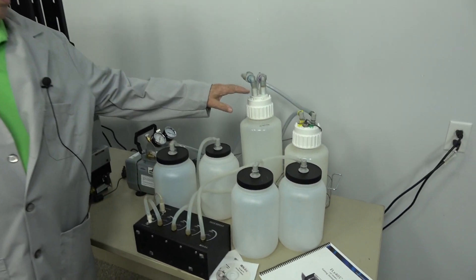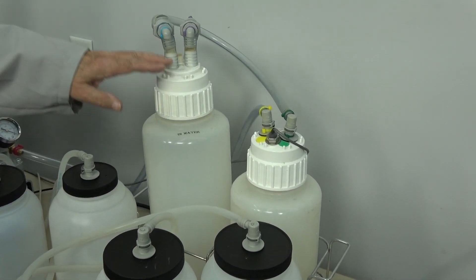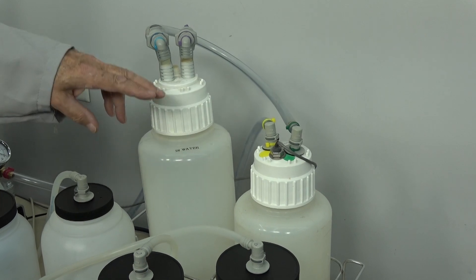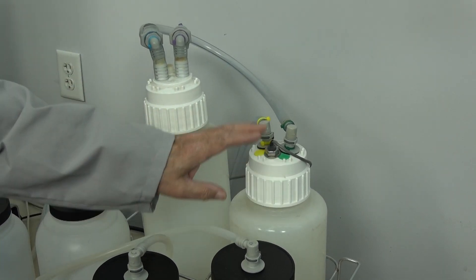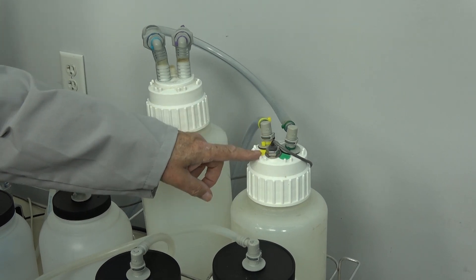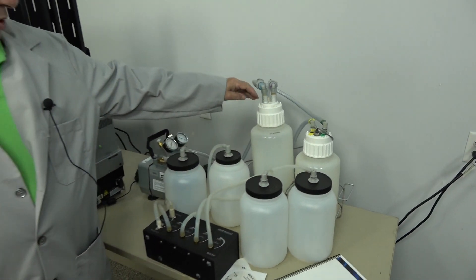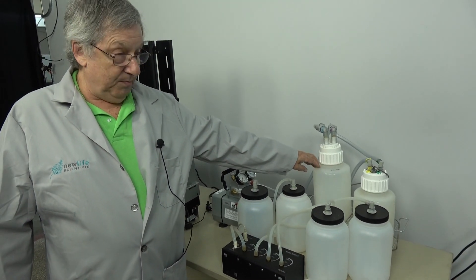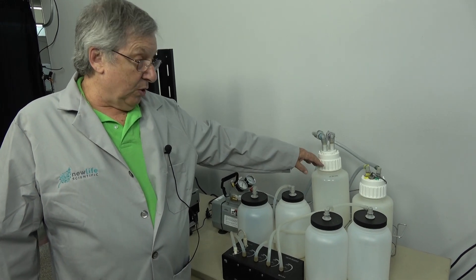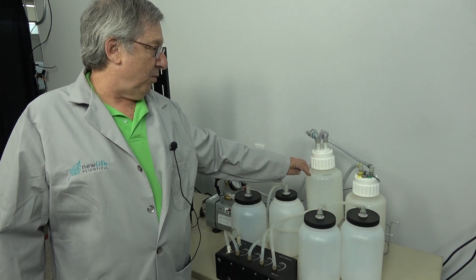Also, we see many of these configured with one bottle rather than two. This one has been retrofitted. It came in with one bottle. And since if you only use one bottle, and this one has the waste sensor, you can only use about half this bottle before it's full. That's not much plate washing. With the larger bottle, and you can even put some three and four gallon waste bottles on here, you can get a lot of water in it. Trouble with the three and four gallon, it gets hard to lift. That's a lot of water.